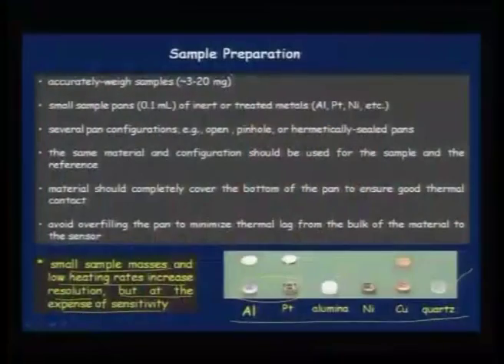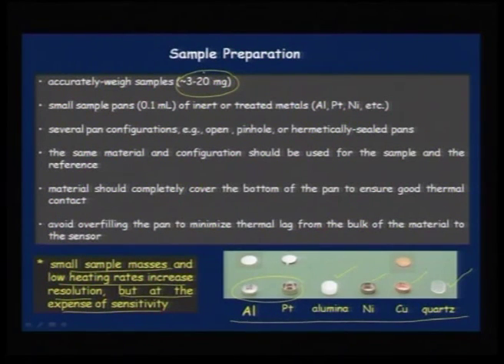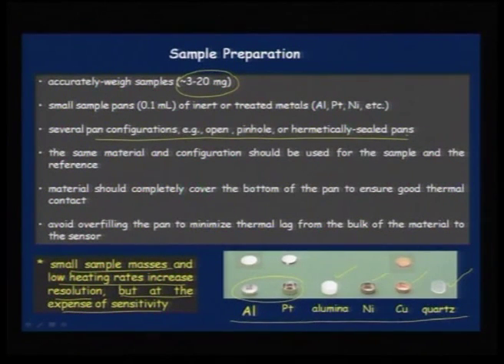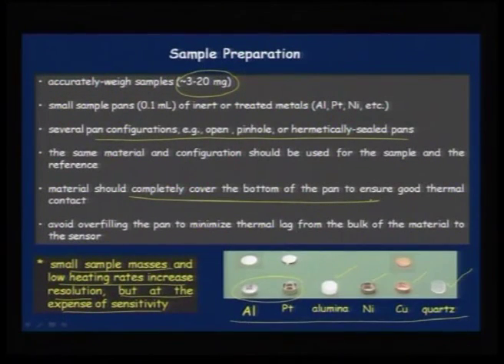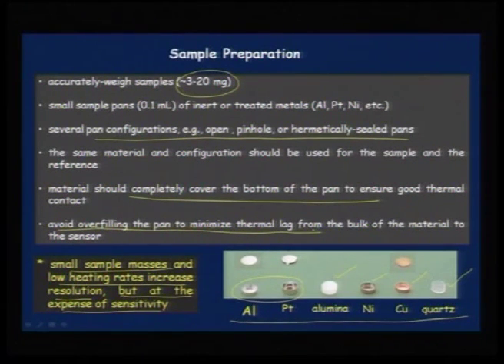Small sample masses and low heating rates increase resolution but at the expense of sensitivity; fast heating rates and large samples increase sensitivity but reduce resolution. Typically 3 to 20 milligrams is taken. Same material and configuration should be used for both sample and reference, and material should be completely covered at the bottom of the pan for good thermal contact. Avoid overfilling the pan to minimize thermal lag.